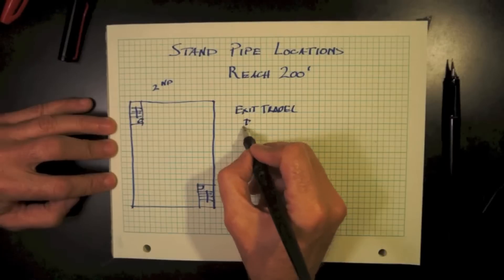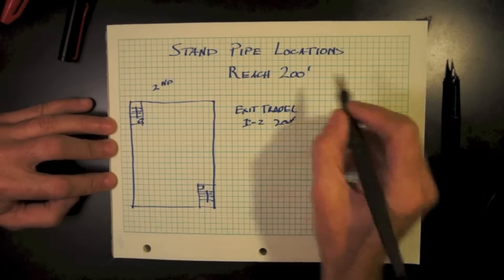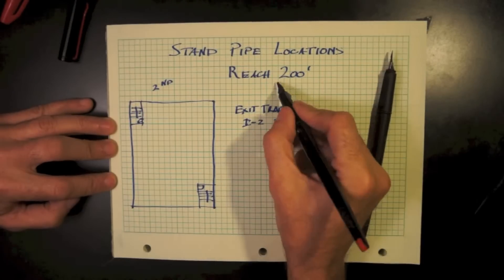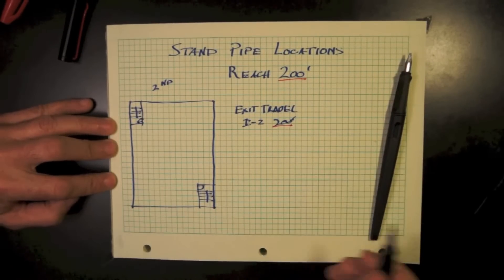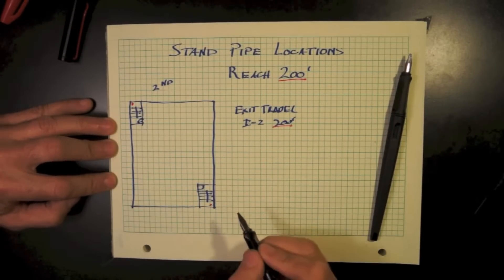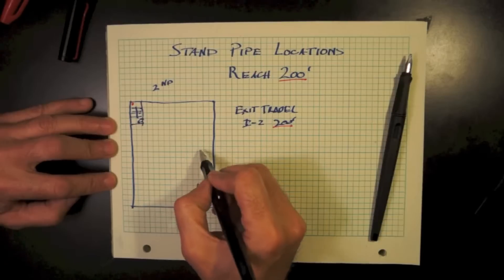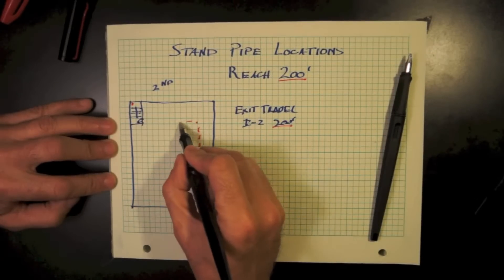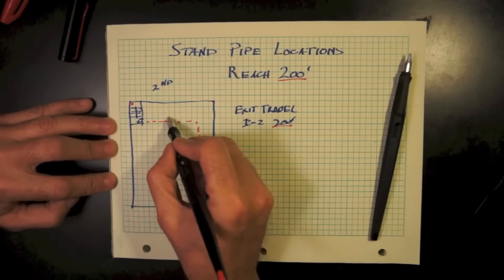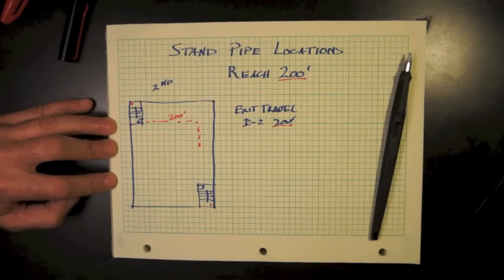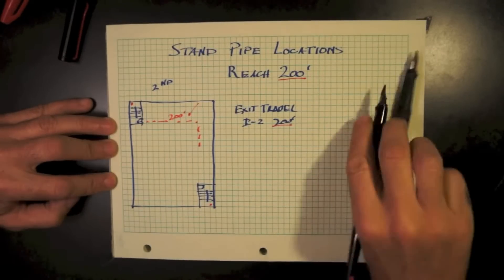Exit travel distance out of I-2 is 200 feet. Every exit stair shall have a standpipe located within it, and most jurisdictions would like that standpipe located at its intermediate landing. This makes it fairly simple. Our travel distance and our access to a standpipe are both 200 feet.